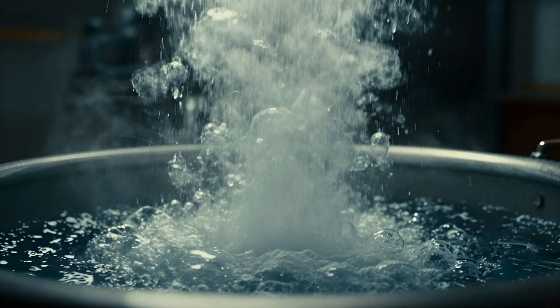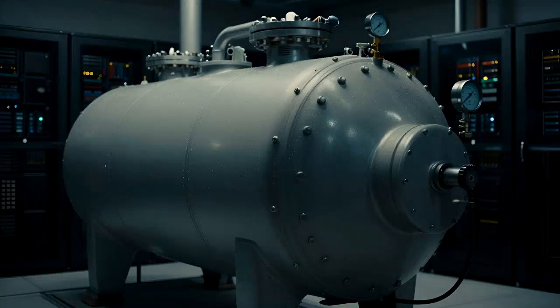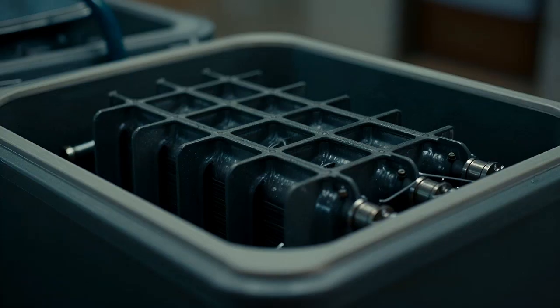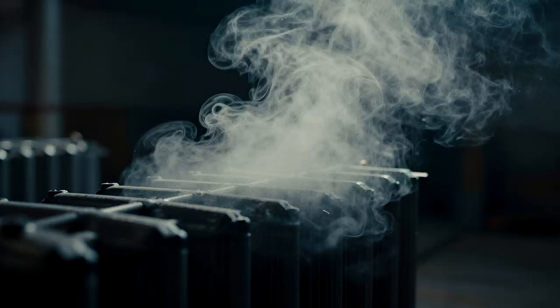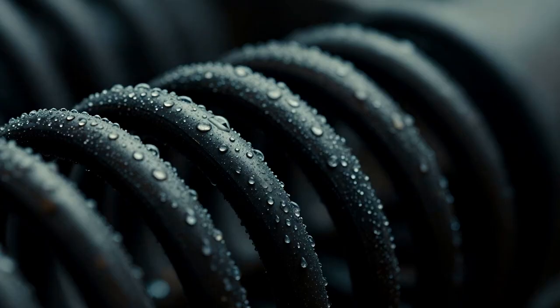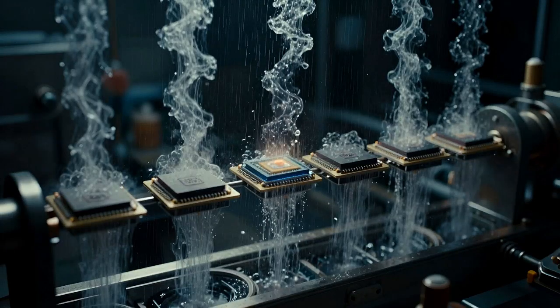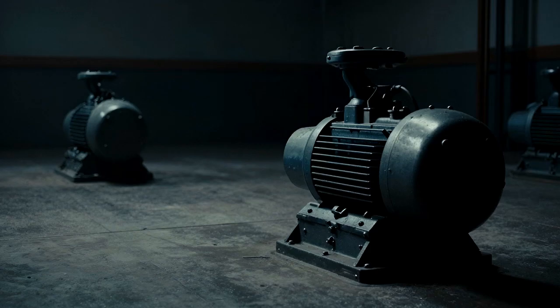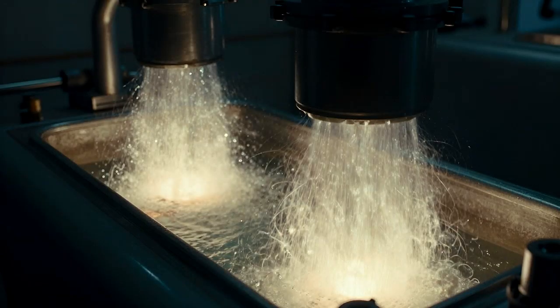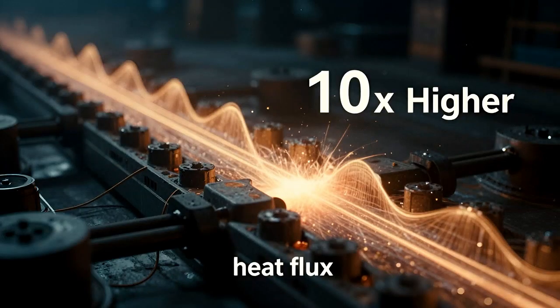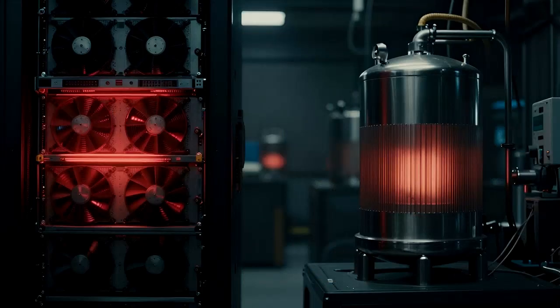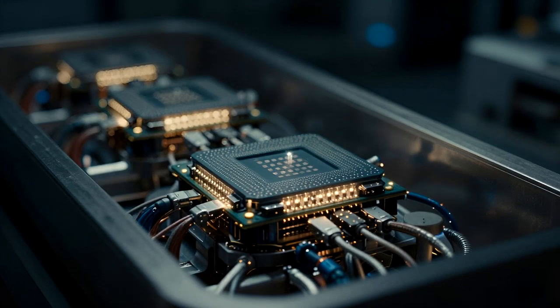The resulting vapor bubbles violently rise to the surface of the tank. Because of this vapor generation, the tank must be completely sealed. At the top of the sealed tank lies a condenser coil, chilled by cold facility water. When the hot vapor hits the cold coil, it condenses back into a liquid state and rains back down into the bath, completing a continuous, self-regulating, passive cooling loop without the need for mechanical fluid pumps. Two-phase systems demonstrate incredible performance, capable of handling heat fluxes 10 times higher than air cooling limits, making them theoretically capable of cooling the most aggressive hardware humanity can invent.